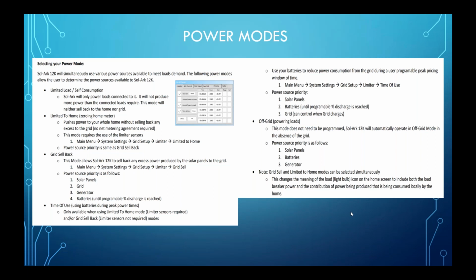There is a Limited Power to Home feature. This is for self-consumption for the whole home, or for the whole project, is how I would like to look at it. What it uses is the external CTs that come with the inverter, and those go in between the main service panel and the utility meter, or just where the utility is coming in from. So it allows us to receive information on the amount of power that the main service panel is using, and it allows us to offset those loads with solar or battery if you decide to use so.